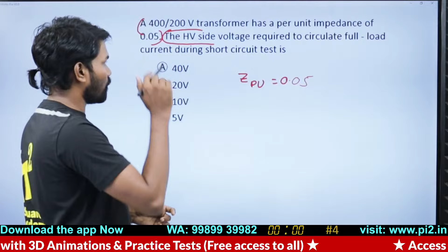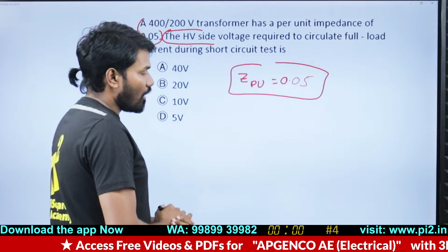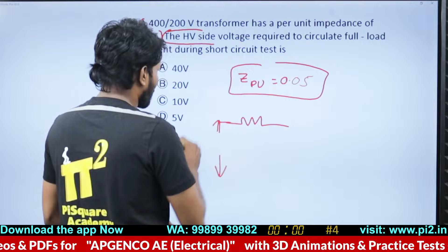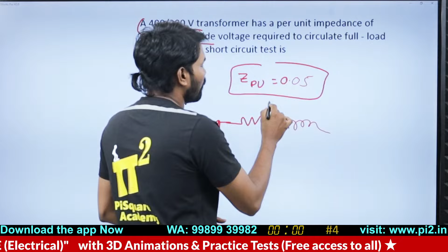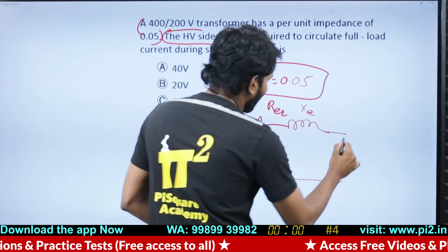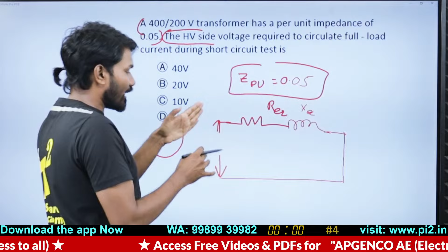Okay, so this is this. Now, HV side voltage required to circulate a full load current during a short circuit test - meaning during a short circuit test, I'm giving at the high voltage side, which is rated at 400 volts. This is the equivalent resistance and equivalent reactance. Now I am conducting a short circuit test - under the short circuit test, how much voltage should I give?